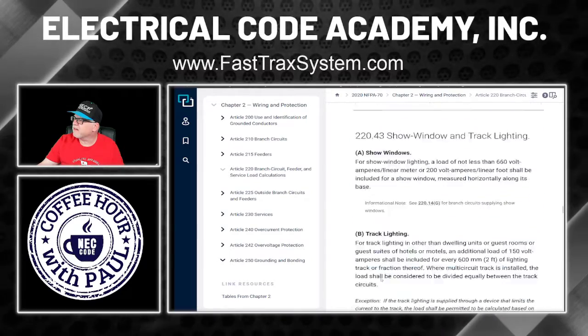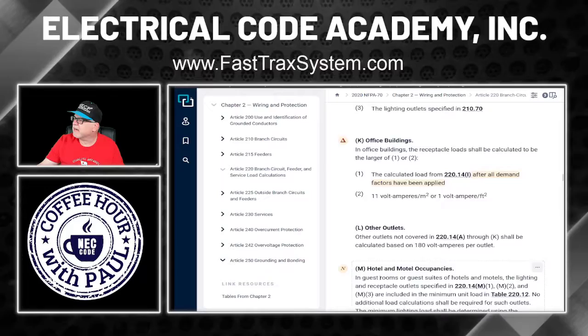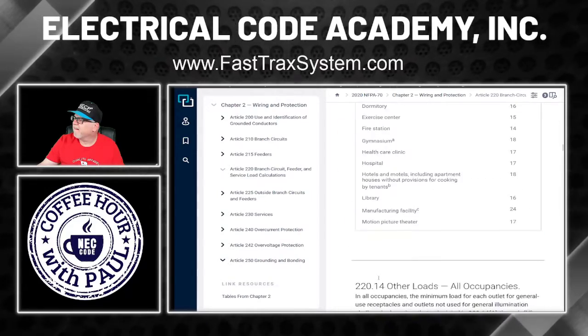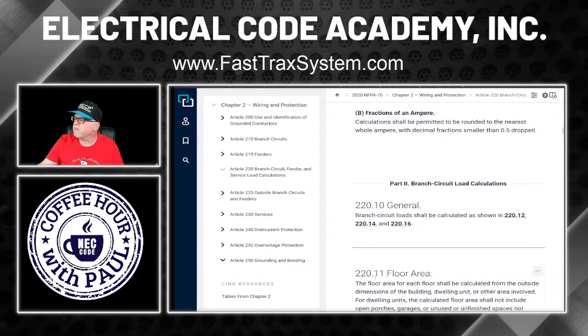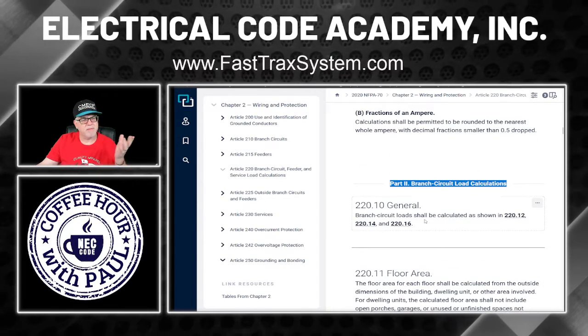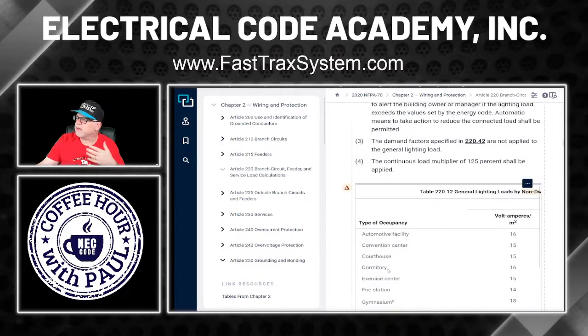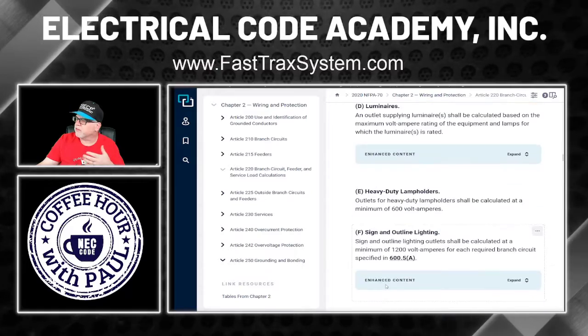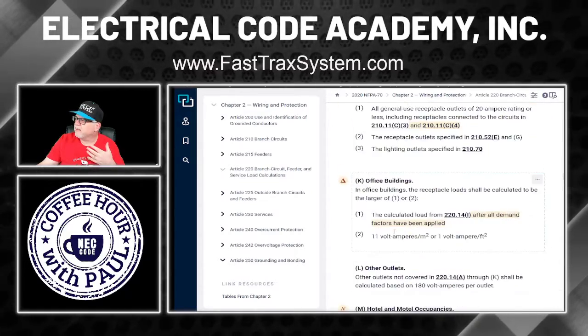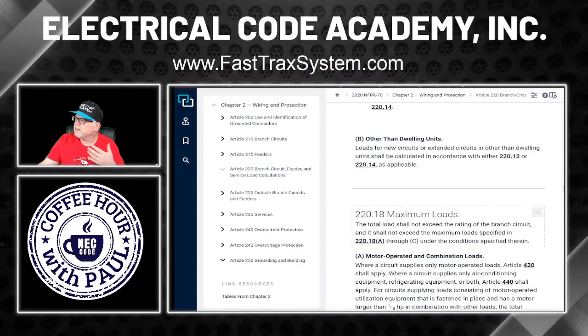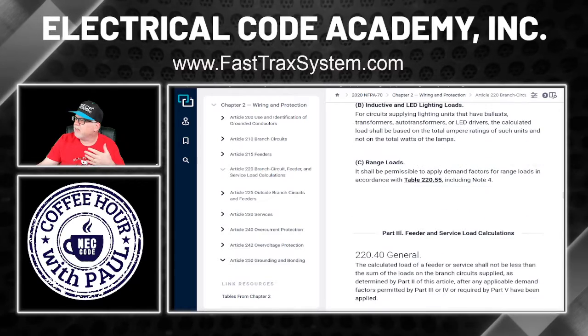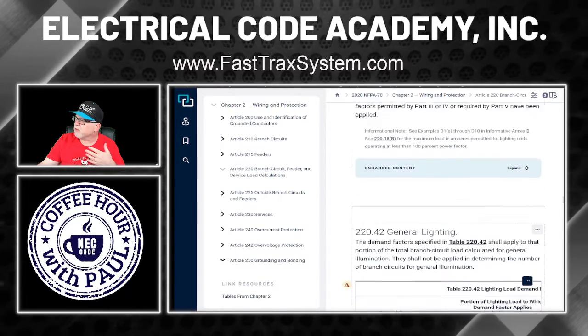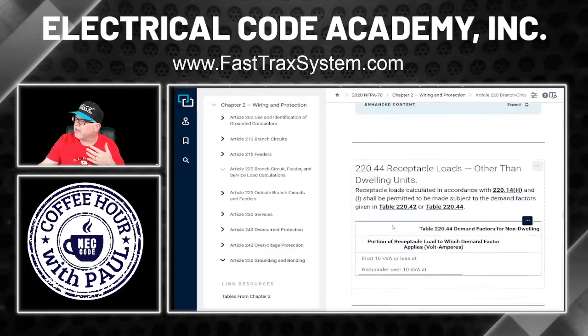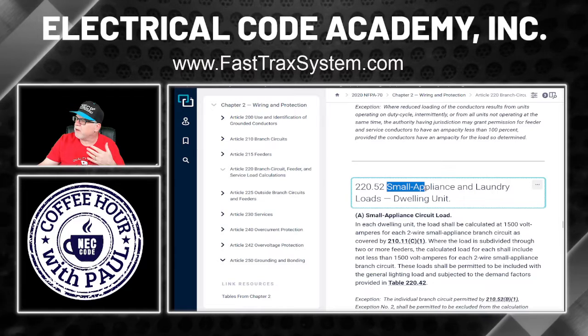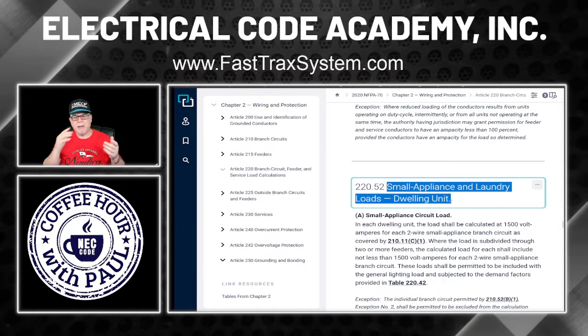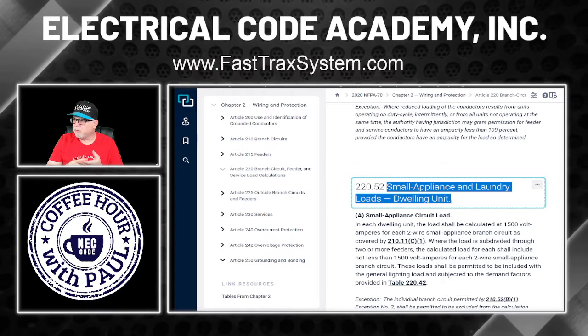Let's see here. Get me back to the beginning of it. Bear with me. Okay, so first of all, let's stop at part 2. So here's our branch circuit right there, and you'll get all the individual things that you need for doing the load calculation right here, and office, hotel, dwelling units, you'll get everything here. And then you get to part 3. In part 3, you'll see all your general requirements, and you'll bold scan. You'll get down and boom, you'll see small appliance and laundry loads for dwelling unit.